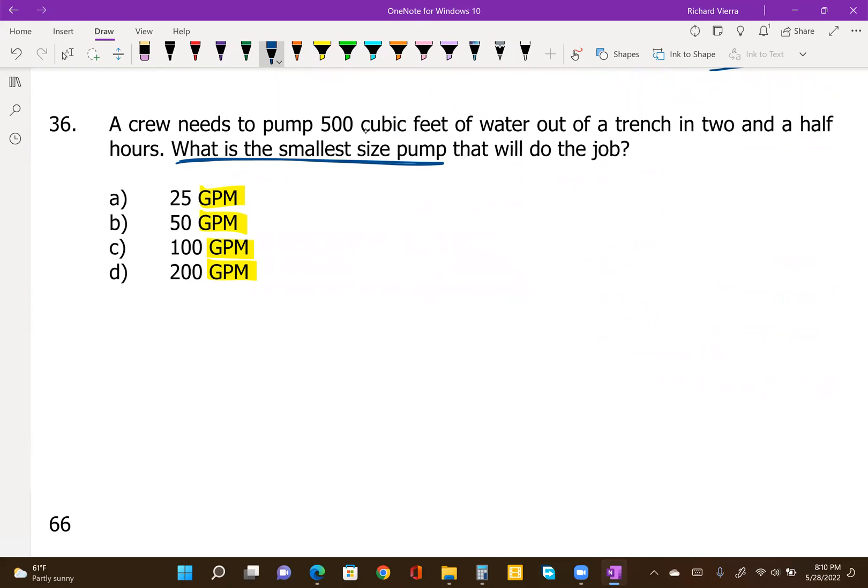But this one we're going to do a little differently because we have two different conversions to perform. To calculate our flow in gallons per minute means gallons divided by minutes. So we get a volume in gallons that we're going to divide by a time in minutes. So our volume, in example number 36, is given as 500 cubic feet of water, which we're going to have to convert into gallons by multiplying by 7.48 gallons per cubic foot. So we take that 500 cubic feet of water times 7.48 to get that number in gallons.